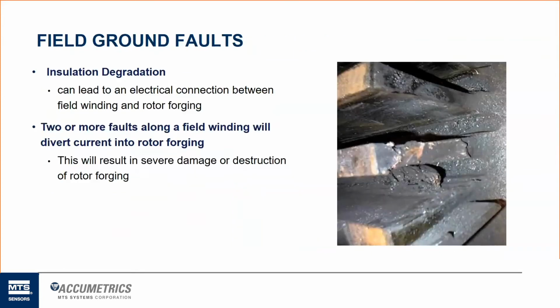So here's an example of a field ground fault. So basically what I was talking about, the insulation degradation can lead to that electrical connection between the windings themselves and the rotor forging. Traditional wisdom has always been, well, if you have one ground fault, it's not that bad because you're not diverting current through one connection. If you have a second ground fault, as the next bullet point says, 2 or more faults will then cause all of your current to divert directly into the rotor forging itself, causing this kind of damage you see over to the right where it's burned in, and it has to then go out of service and be repaired. It can lead to a lot of destruction and damage.